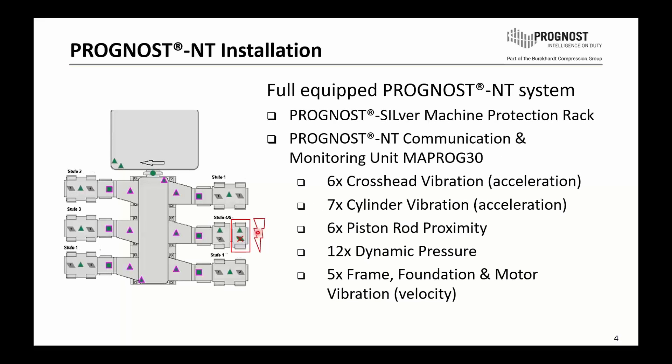The Prognost system used is a Prognost NT with the silver machine protection rack. The sensors used include crosshead vibration sensors, cylinder vibration, rod position sensors, dynamic sensors, dynamic pressure sensors, and also frame, foundation, and motor vibration — nearly the complete equipment of a typical Prognost installation.